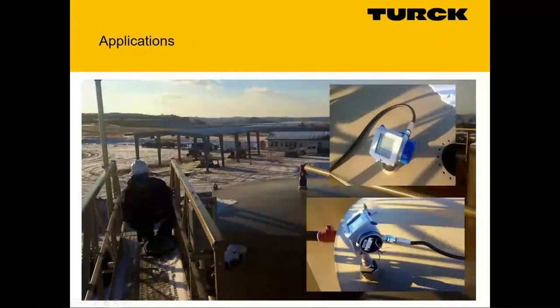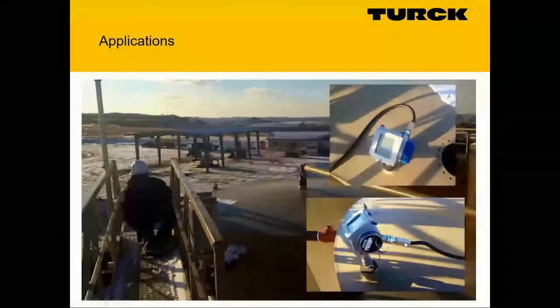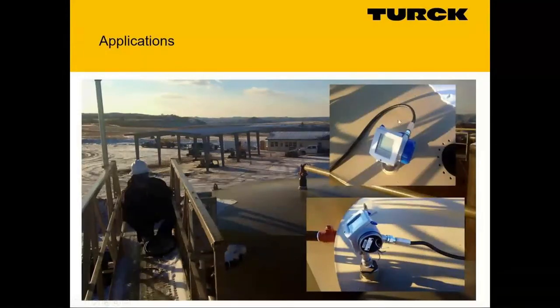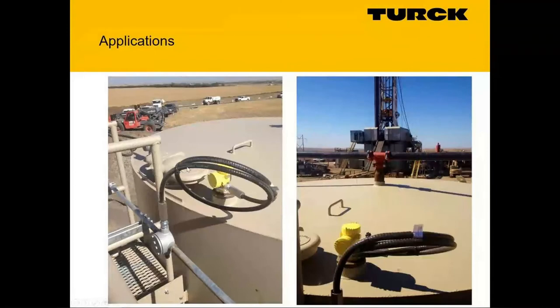We do have some Div 1 cables. This is a Div 1 location — it was probably minus 40°F wind chill when we were helping put these in. We have a factory-poured seal in this fitting, done in our Minnesota factory. We have two versions: one with the MCHL cable and a new high-voltage flexible cable that achieves the same thing. Things were breaking — covers were breaking off instruments — so with this union we could pop it in, fit the wires, and done. No seals to pour, saving a lot more time in the field.